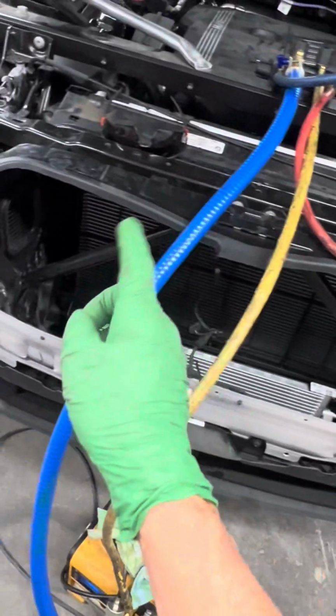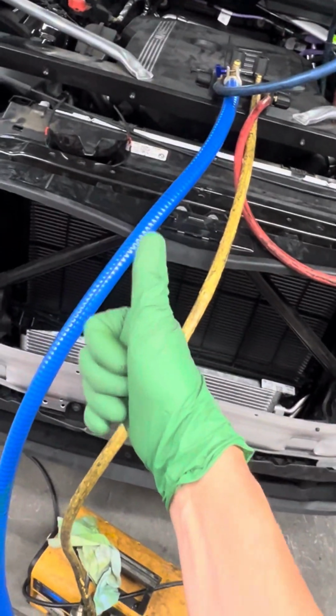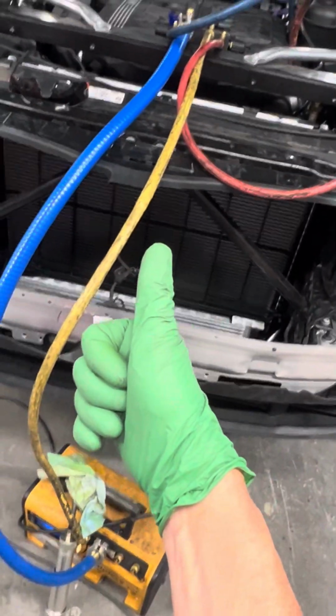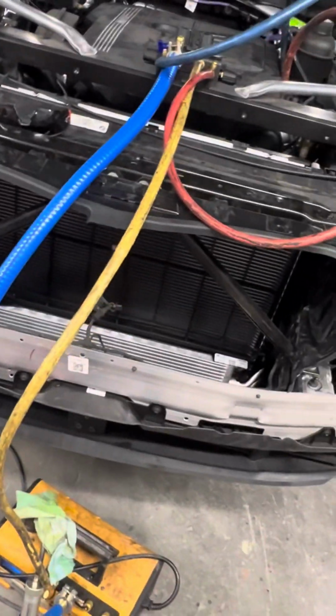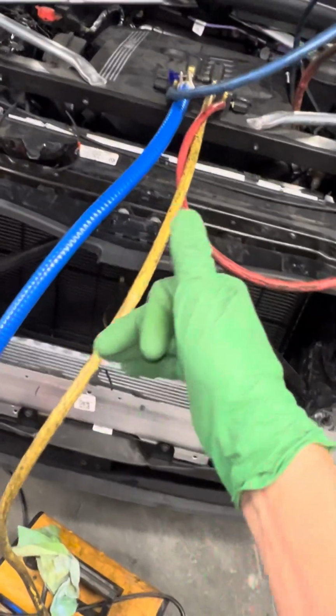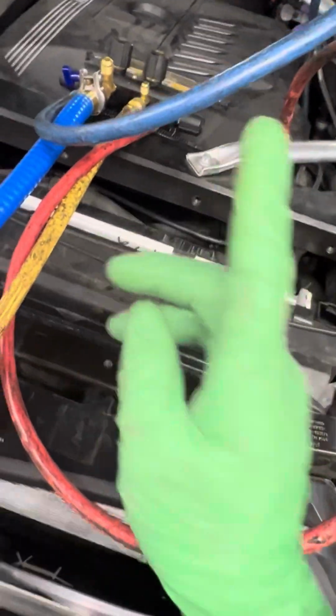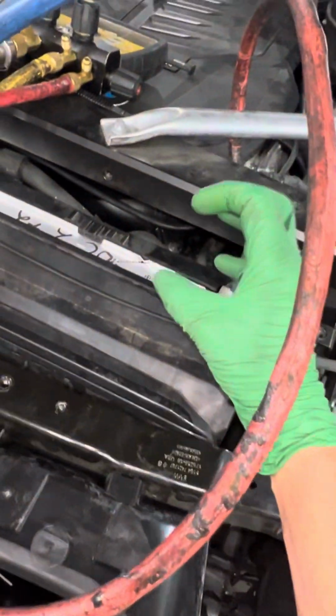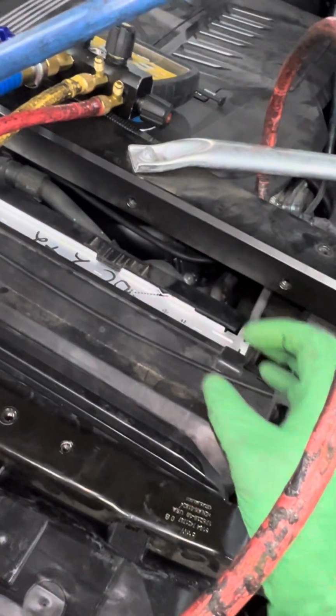And many, if someone's going to go by that rule of thumb - the thing that gets you in trouble all the time - they say 45 milliliters is a standard they've seen written down, and they're just going to go by that. So you end up sticking about 1.5 ounces of oil on top of 3 ounces. That will give you little issues because you have an extremely small, tiny system here, especially if you only have a single evaporator.